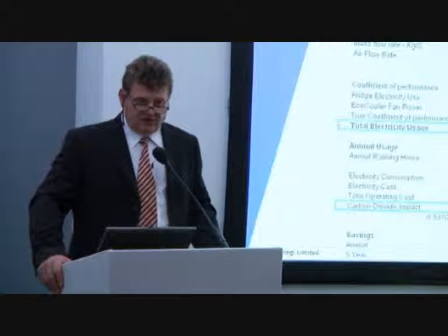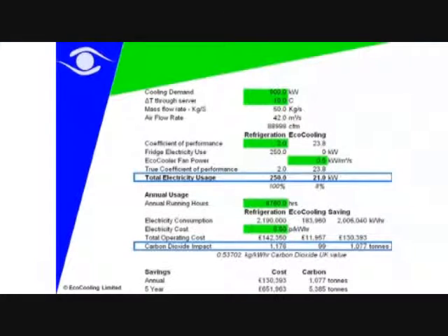8,760 hours in a year. We can't get away from 24/7, 52 weeks. A lot of hours. So the M247 project, if they'd have gone down the existing conventional CRAC route, would have been using over 2 million kilowatt hours of electricity per year. The eco-cooling system would require less than 200,000. And at 6.5 pence a kilowatt hour, their annual running costs for the CRAC system would be 140,000 compared to just over 10,000 for an eco-cooling system, with a potential environmental benefit of saving over 1,000 tons of carbon as well. Big numbers.